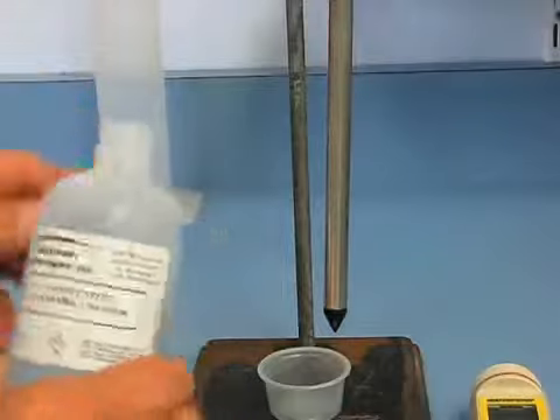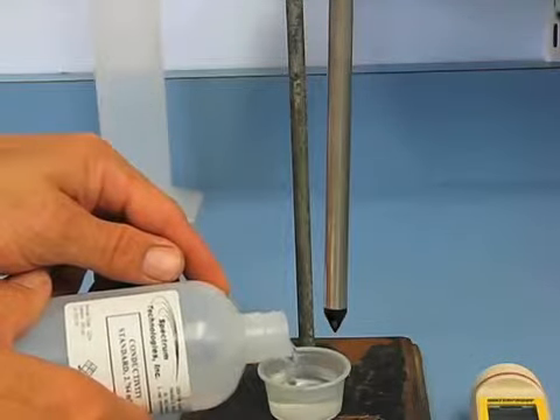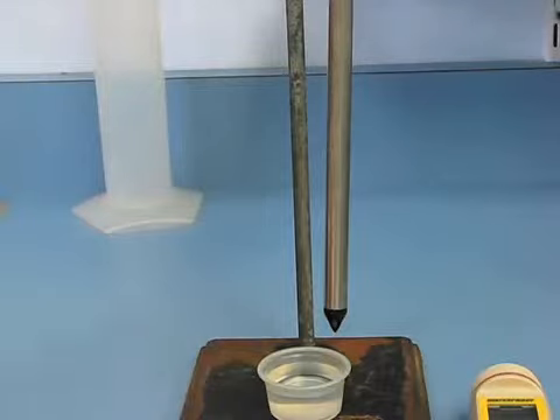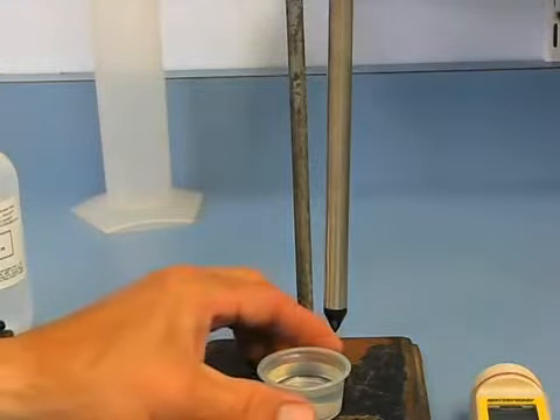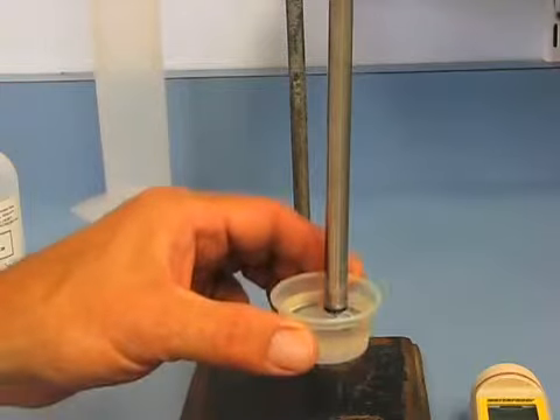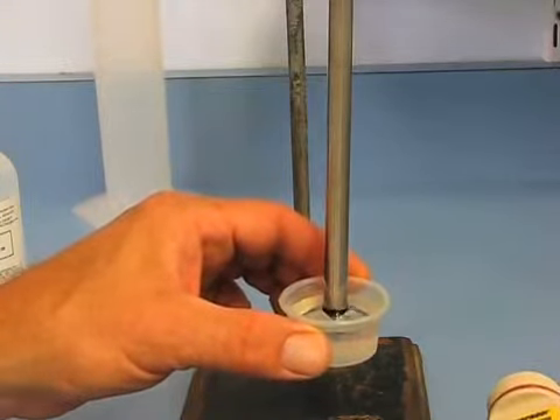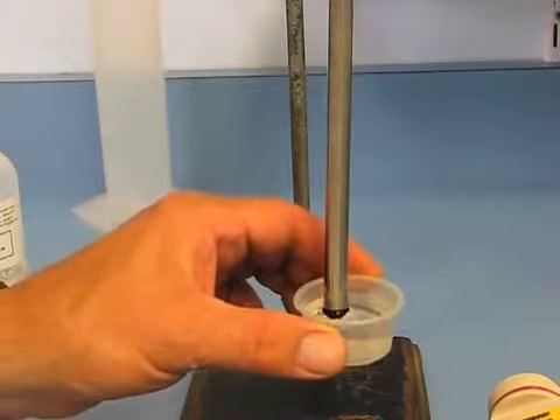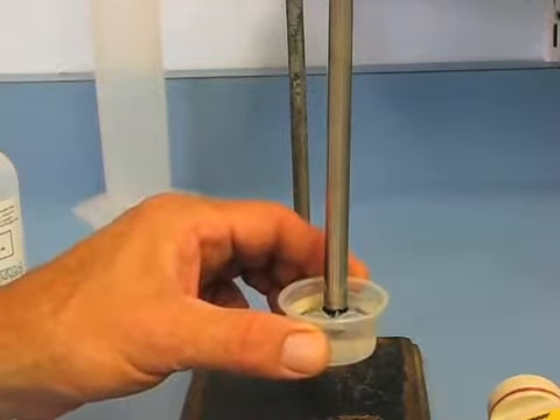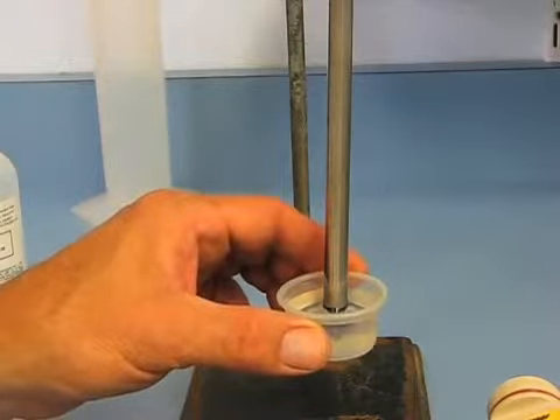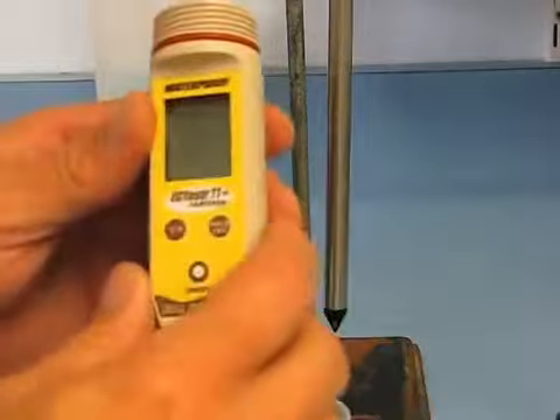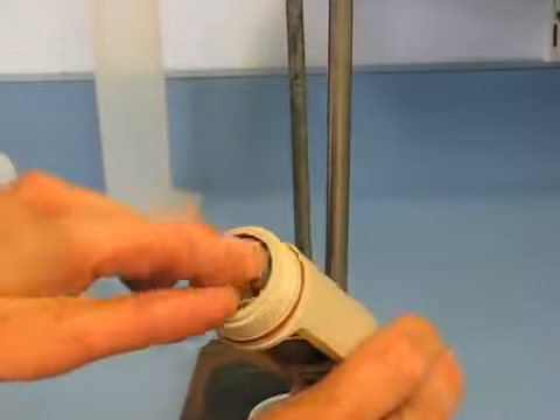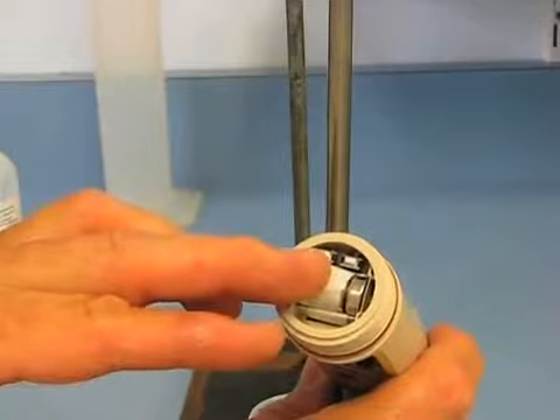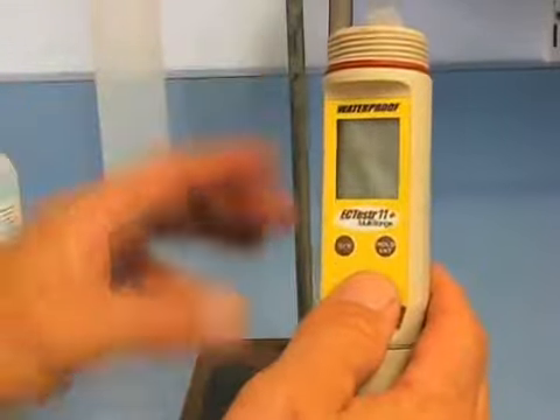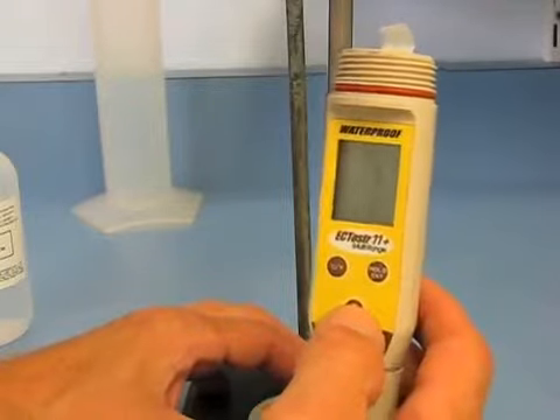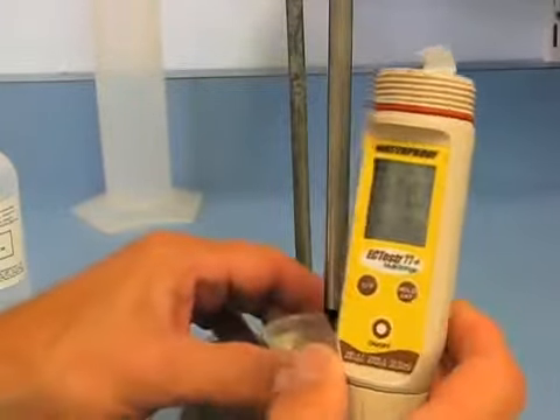What I like to do is pour a little bit into a small cup. This is like a salsa cup. If you go to Mexican food restaurants, sometimes they'll have some of those left over. You take a few of those, and you just immerse the probe into the end of the solution, and don't let the probe touch any of the areas of the bottom or sides of the small cup when you're doing this calibration. So all you need to do is take your meter. You've already taken the top off, as we described earlier. The increase button is on the right, decrease button on the left. When we turn it on, we'll get a reading when we put the probe into the solution, and we'll adjust the reading to match that 2.764 reading.